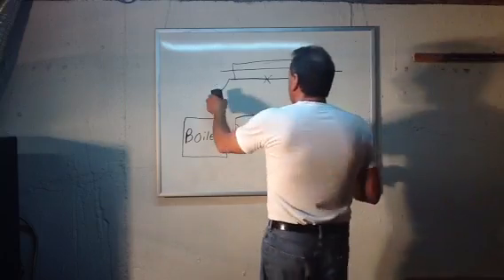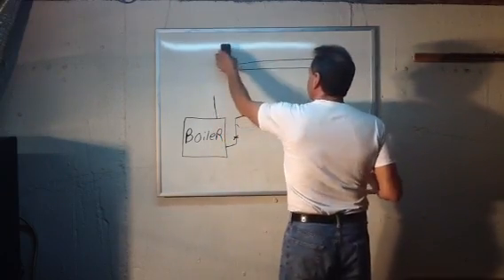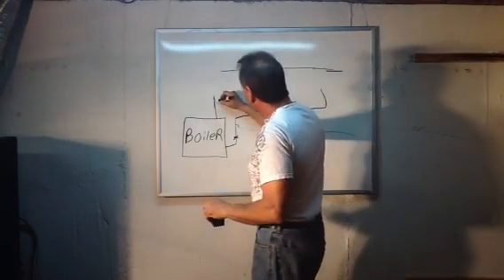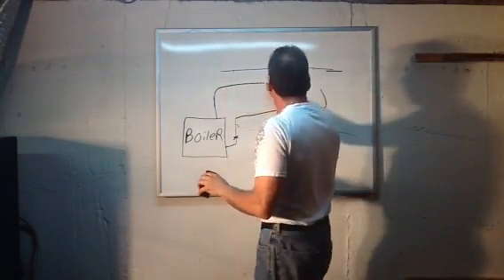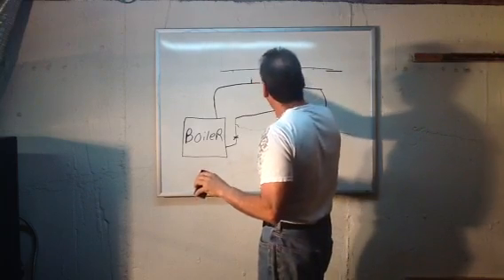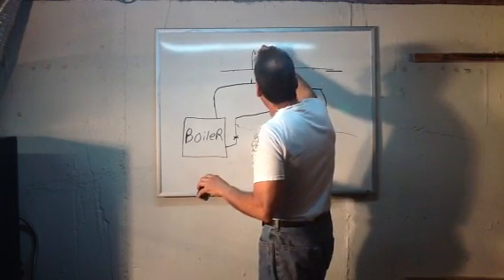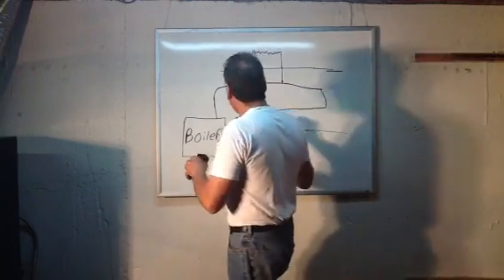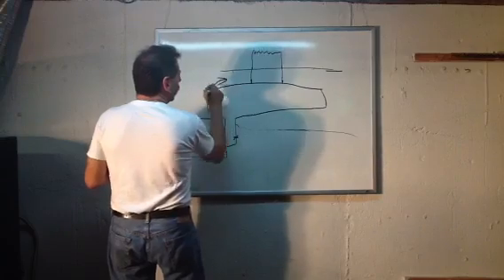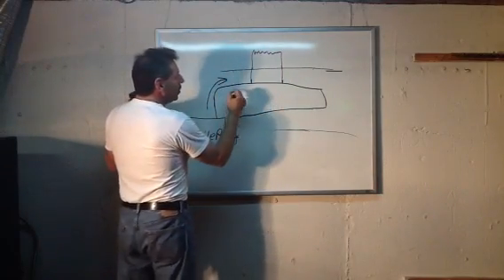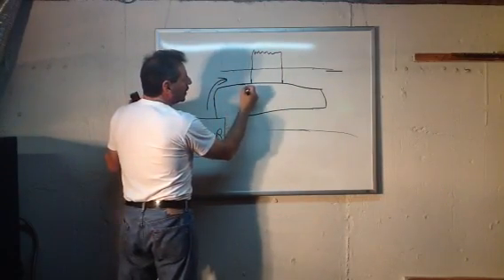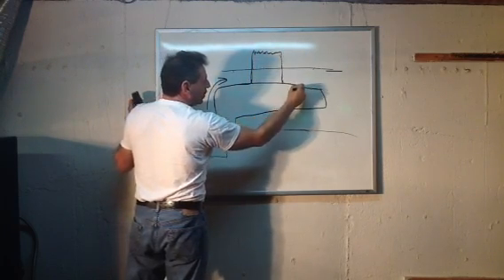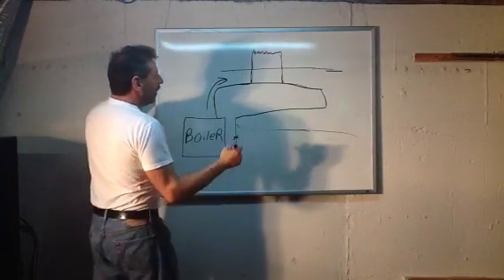Another scenario is radiators off a monoflow tee. Same thing, they got a monoflow tee or just a tee and there's a radiator up here. They'll put a bleeder on the radiator. Now don't forget the flow is this way, the water flow is this way. When you do this, the water actually goes in here, travels through the radiator, heats the room, comes back down and continues.